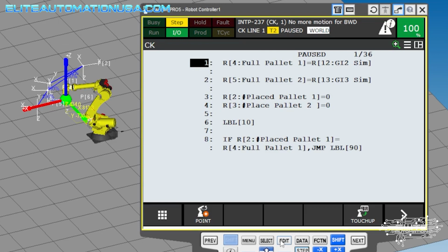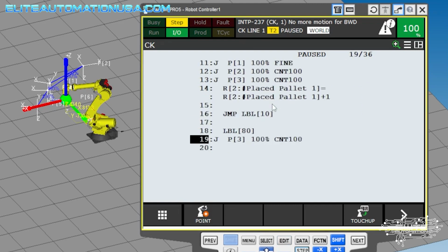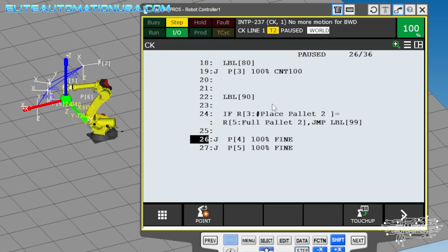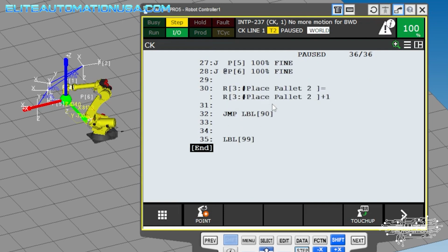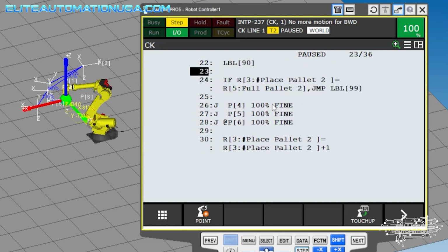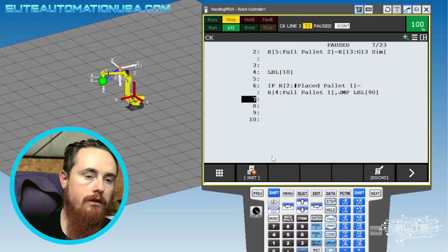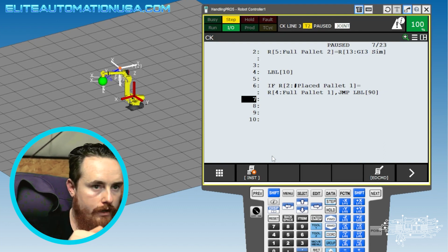One other thing to keep in mind, no robot program ever ends unless it's set up in a way where there's something that restarts the robot program. But almost always the robot program never ends, it just runs in a continuous loop. And then it's just commanded to do different stuff off of that one loop. So if the robot's not being commanded to do something, then it just sits there and just keeps scanning in the loop. Waiting. Oh, PLC said part present, go. And that will trigger the signal for the robot to go pick.